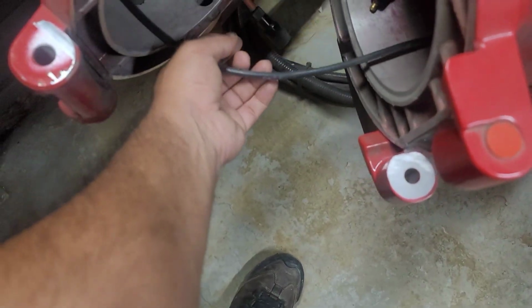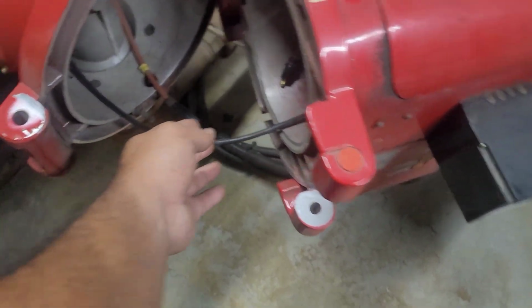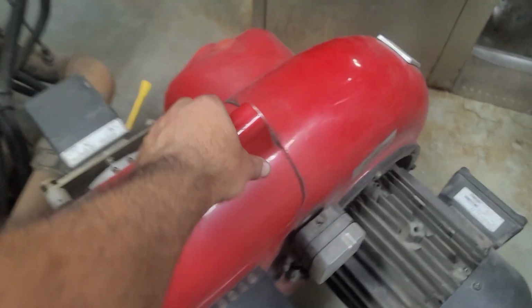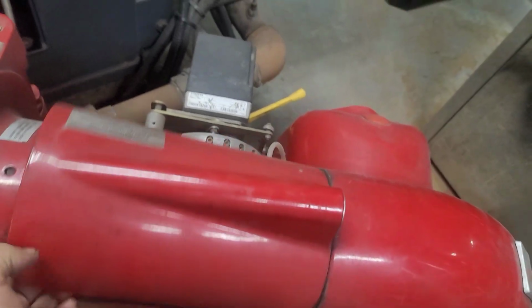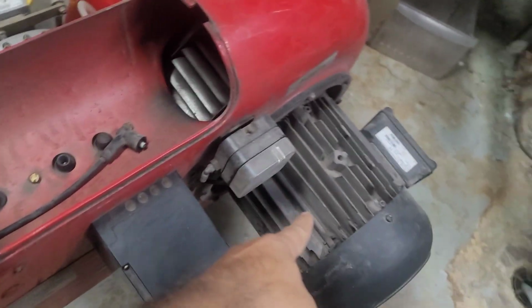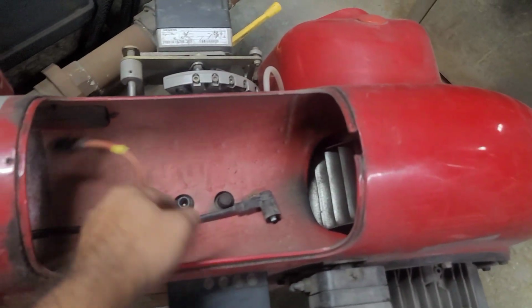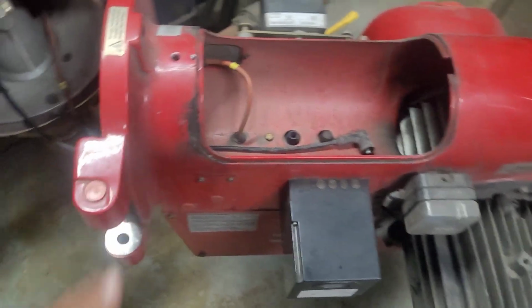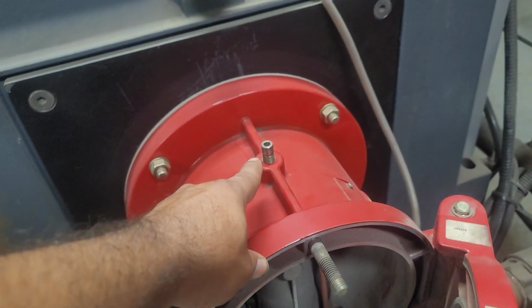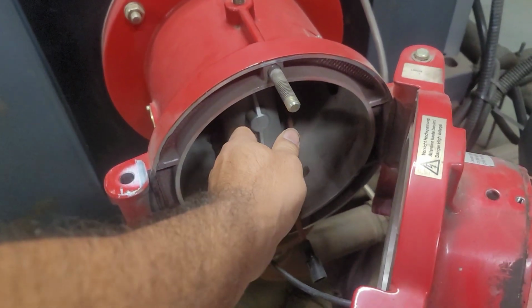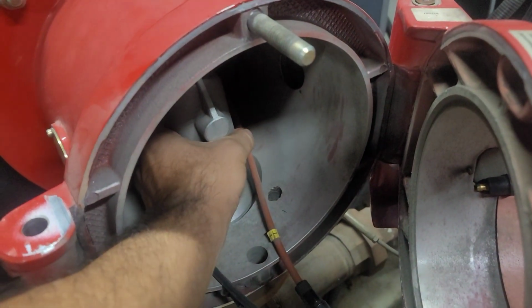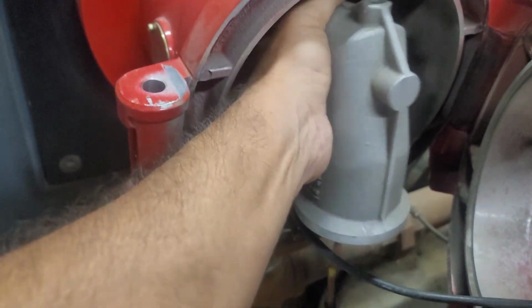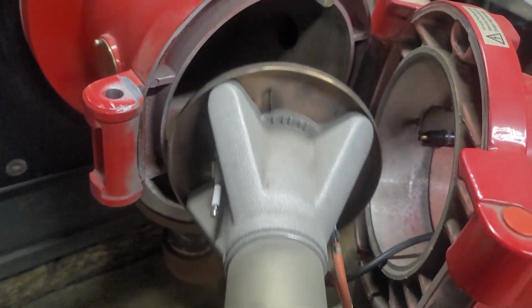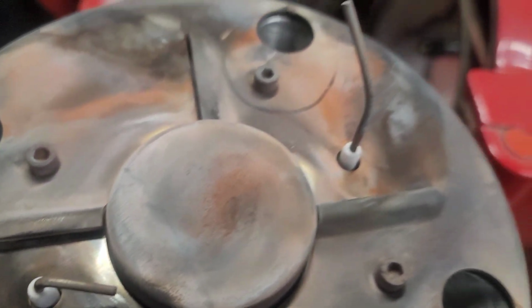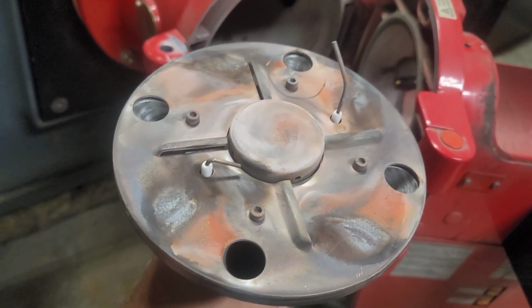Okay, so we have igniter and the flame rod wires. I have disconnected it here, but the access is here, so we can just lift this thing. So that's the blower motor, and I have disconnected the igniter and the flame rod wires. So this is the burner, so we have to remove this Allen bolt, and the whole thing will come out. Okay, so I have removed the Allen bolt. So that's our burner, that's the igniter, that's the flame rod, and the whole circular plate is a burner.